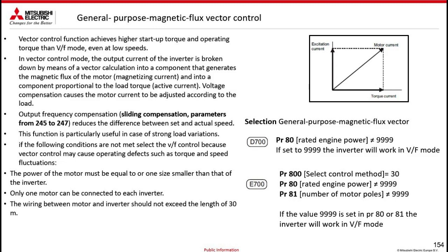vector control. Once all the parameters are defined, I perform this auto-tuning procedure, which is automatic. In the FRD inverter, it is static, just like in the FRE 700, but in the FRE 800 and the FRA 800, for example, it is also dynamic. So you can put the motor in rotation during this auto-tuning procedure, where we get information such as rotor resistance, torque current, excitation current, stator resistance, and so on. With the vector control, especially with the general purpose, for example, you get a significant increase in torque, and in fact, it is often appreciated.